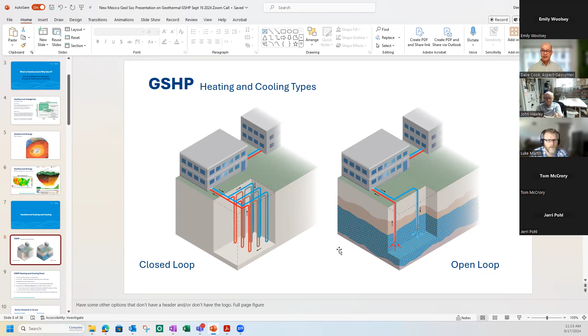It can be limited because you need a lot of land at these high heating and cooling load facilities. Here's what we're focused on. We design both types of systems, but here's where we're finding a lot of advantages: if there are aquifers present, then we'll remove groundwater through an extraction well, run it through the heat pump, heat or cool buildings, and then push that water back down into that same aquifer. It's a closed system, although we call it open loop, there's no net loss of groundwater. Much more efficient than a closed loop system and can be scaled over time.